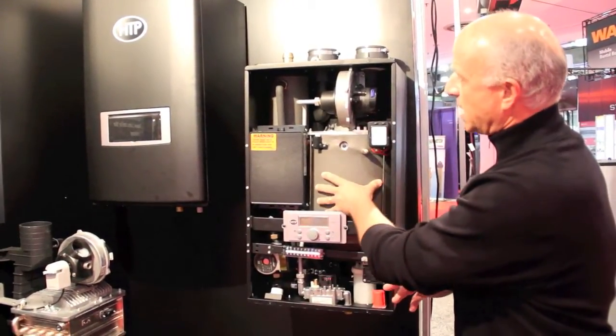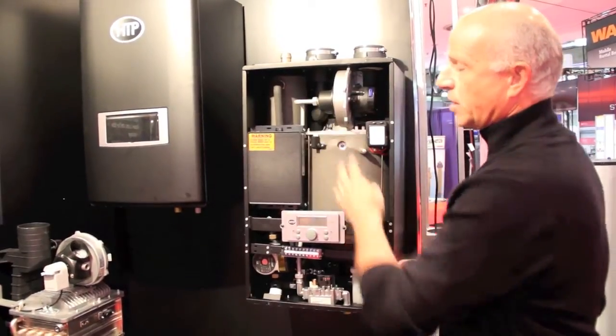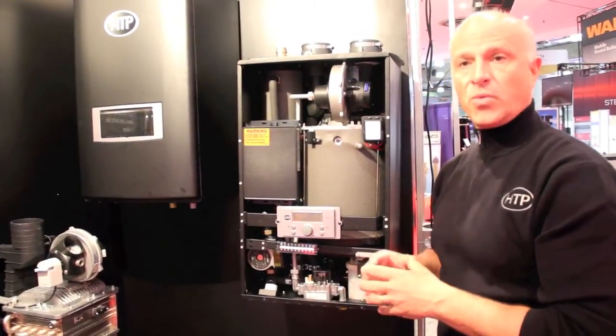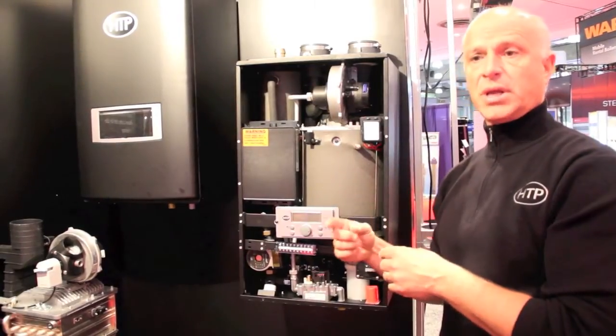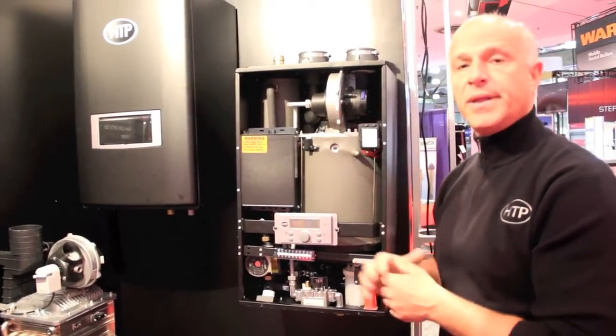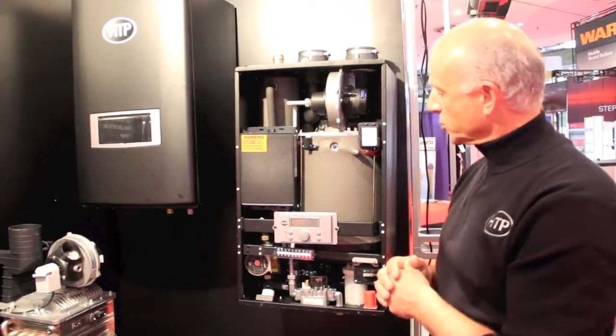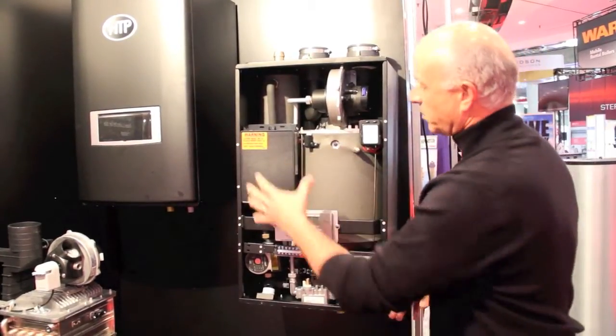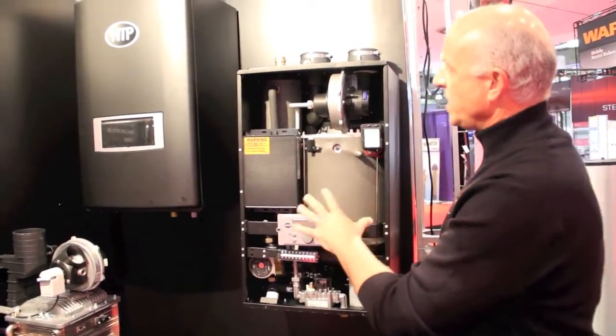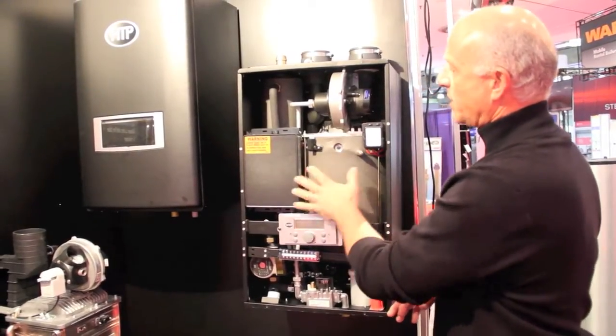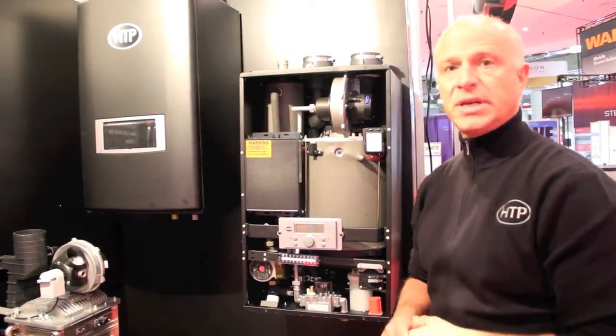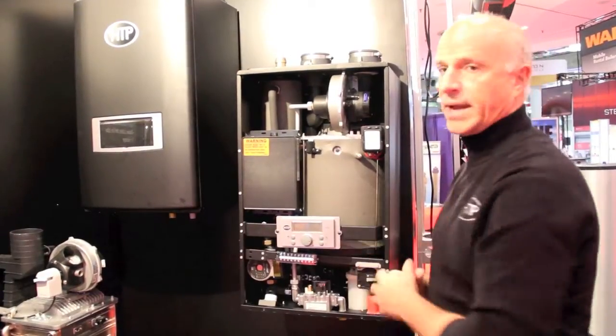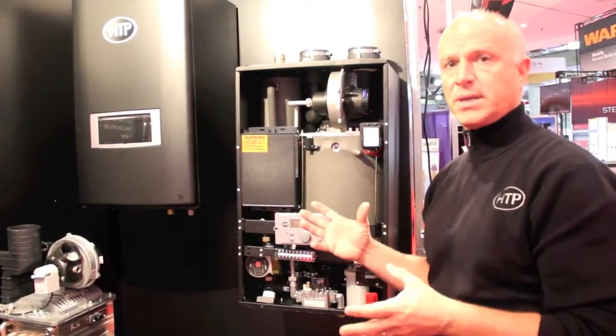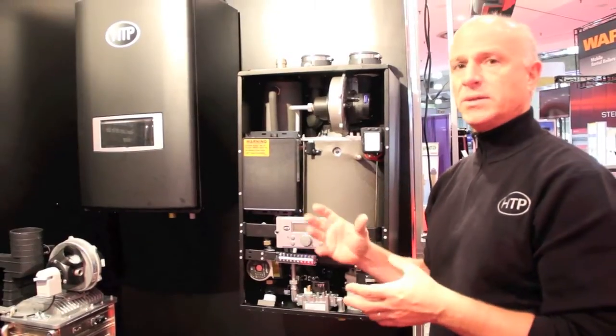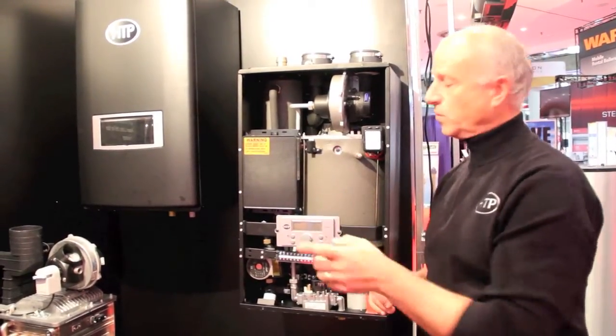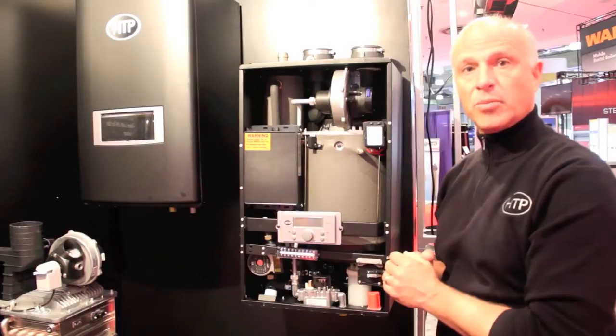Again, the fire tube design with the indirect hot water cylinder where we're circulating the boiler water through the cylinder, and then we have a stainless steel coil in there that transfers the energy. We're also, as you can see, everything is placed in the front. One of the unique features with this electronic system and the combustion system is we have optic sensing as far as monitoring the flame. A lot different than what you're used to with other appliances where we have flame rods. This actually uses optics both on the floor and on the wall hung boiler.